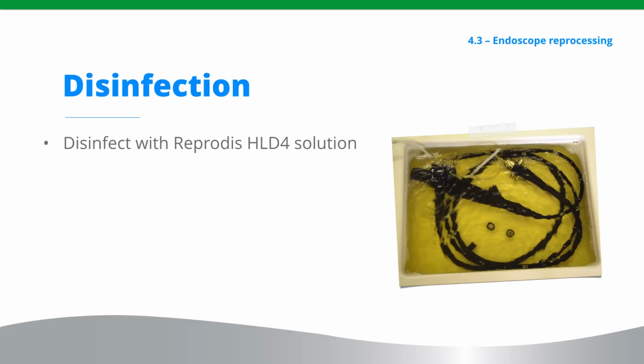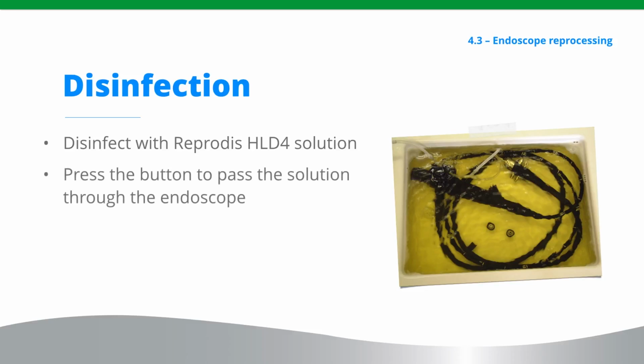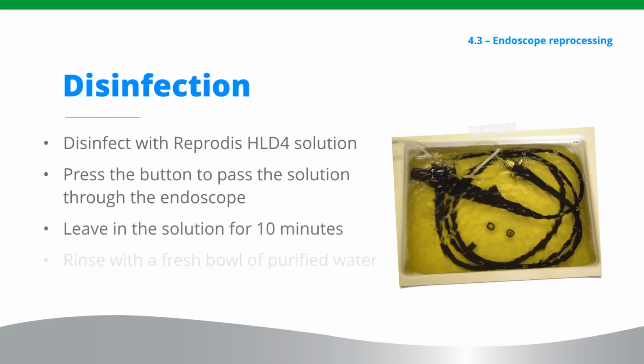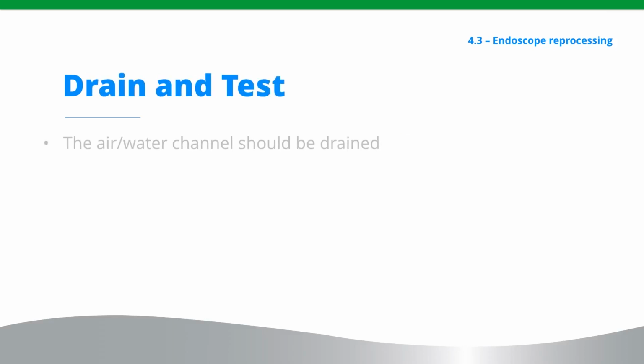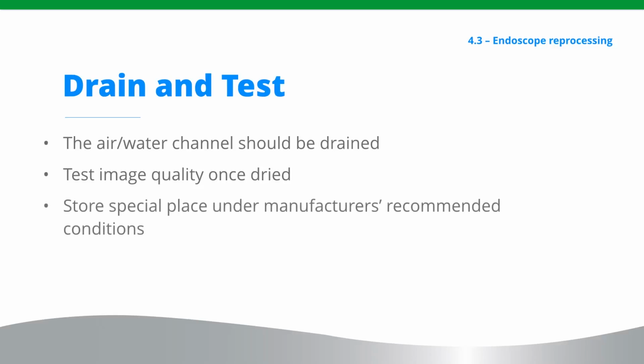Disinfect with Reprodis HLD4 solution to maker's dilution by pressing the button and passing the solution through the endoscope until it emerges into the aspirator bottle or syringe. Leave the instrument in the solution for 10 minutes, then rinse as previously with a fresh bowl of purified water. The air-water channel should be drained. When all processes are complete and the instrument is externally dried, the instrument can be tested for image quality and stored in its special place under manufacturer's recommended conditions.